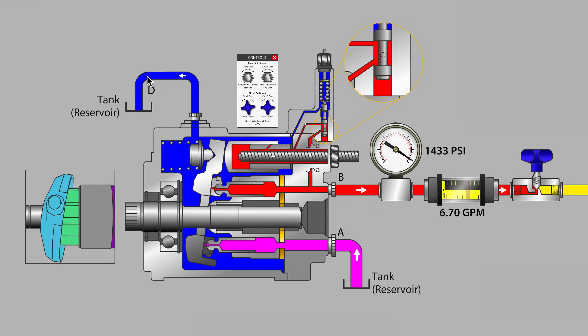Obstruction on the case drain line could reduce or stop all of those flows and the pump could very quickly move to catastrophic failure without that critical lubrication.